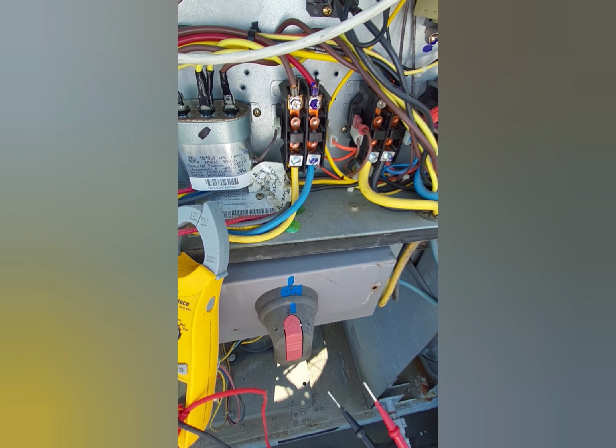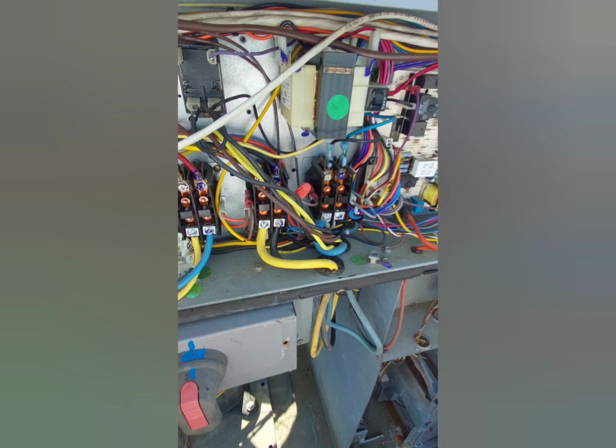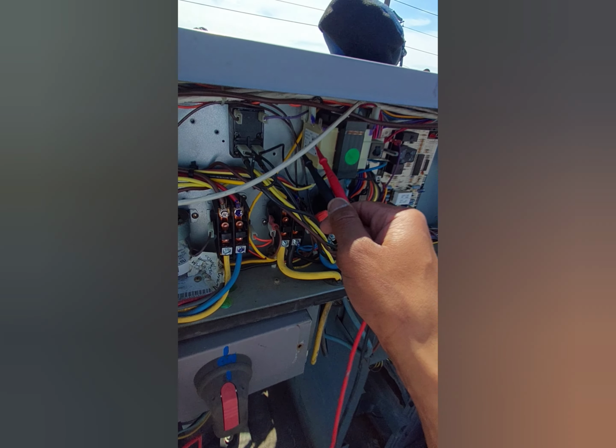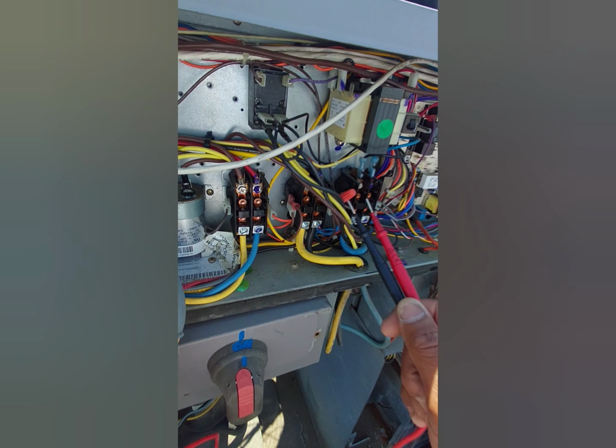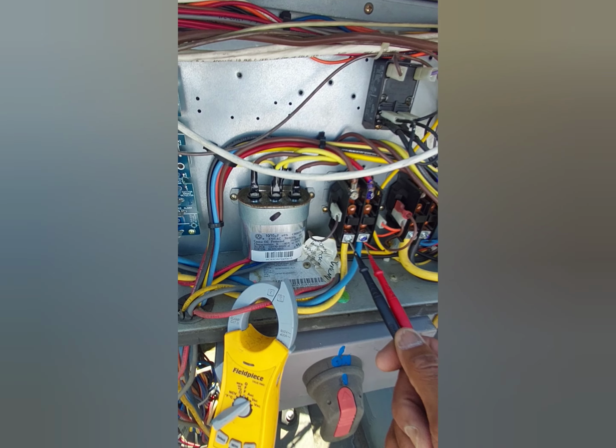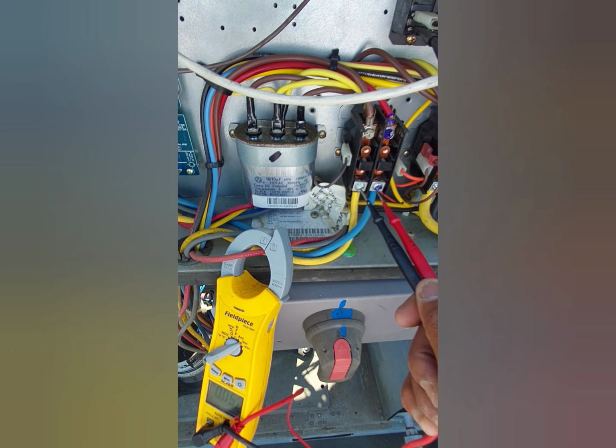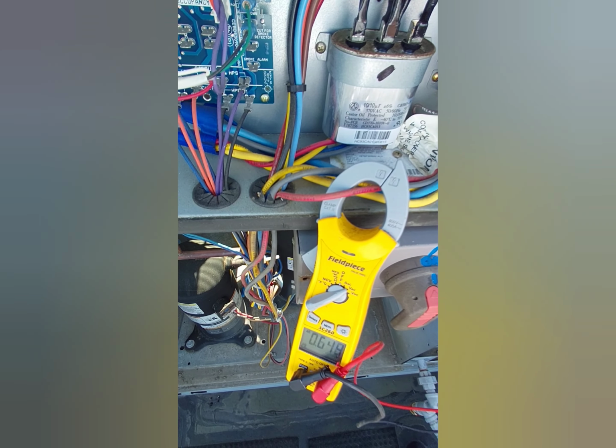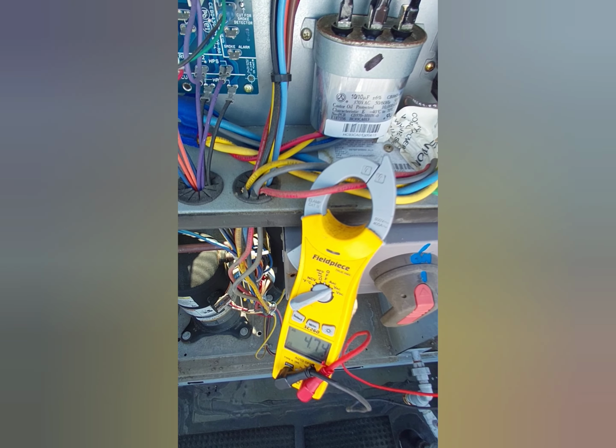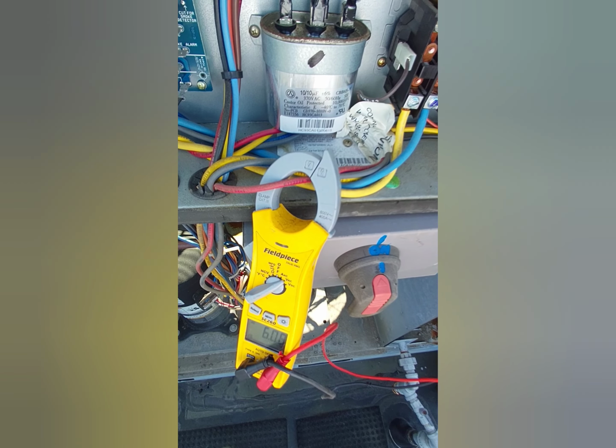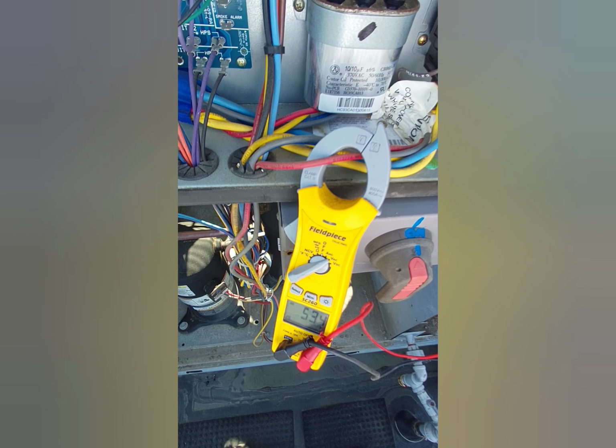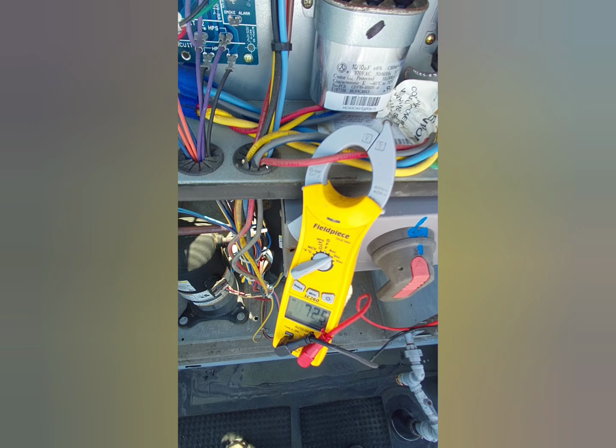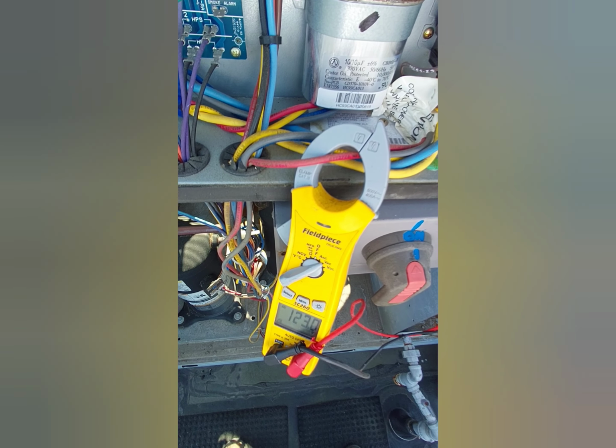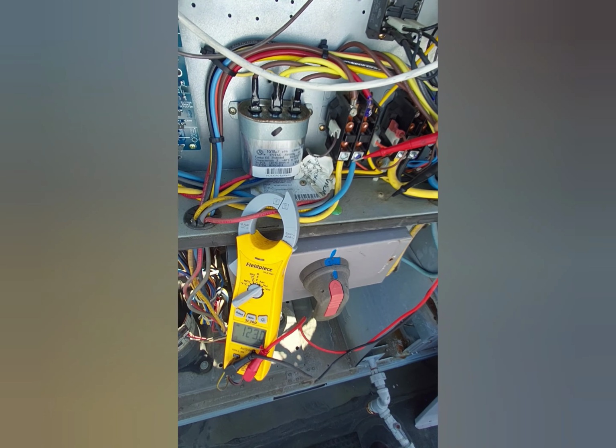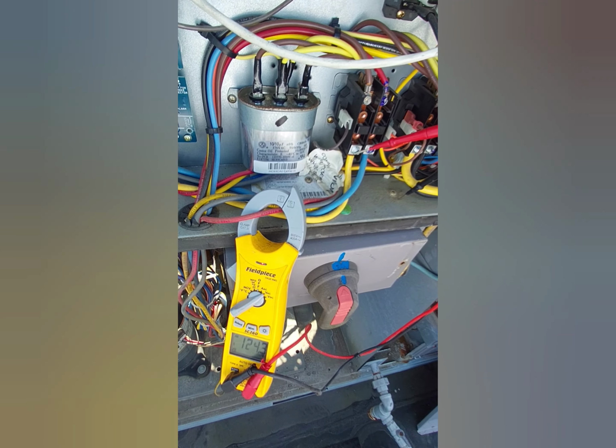So push the contactors in, everything's humming. Transformer don't got 208 volts, it got 8. Shit's not making no sense. But from one leg to ground, I got 120.